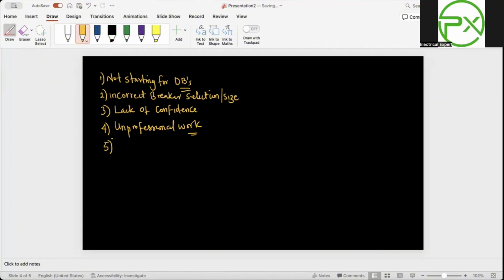Number five, using incorrect cable sizing. If you're not using correct cable sizing - 2.5mm is different from 4mm, and different from 6mm - it looks similar, but you have to know which one to use and which not to use. If you are connecting an AC above 2.5 kilowatt, you use 3 core 6mm square cable. If you are connecting an AC below 2.5 kilowatt, you use 2 core 6mm square cable plus 1 core 4mm square cable for grounding.